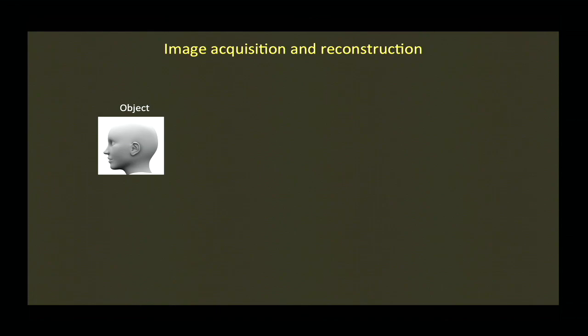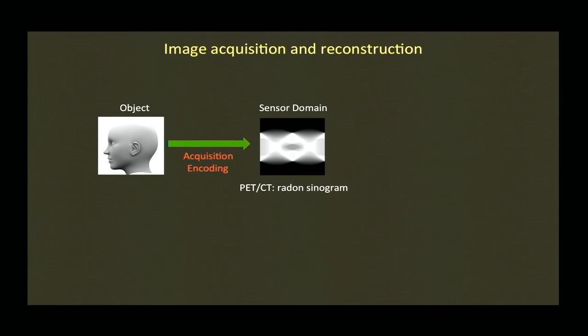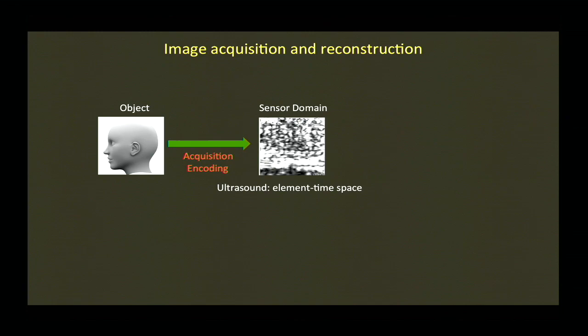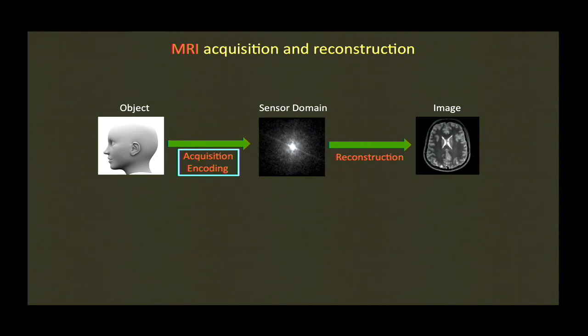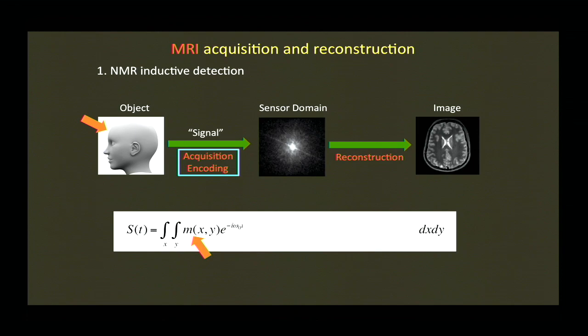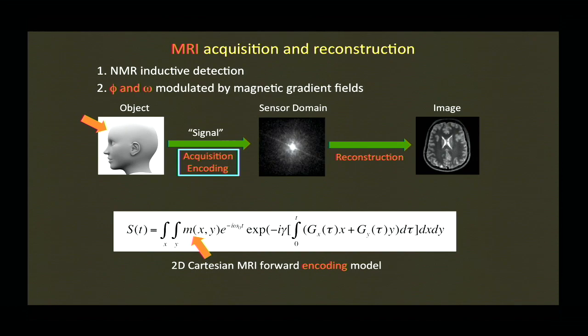To understand how we approach this, let's look at imaging independent of modality. You start with an object, forward-encode it into an intermediate representation — the sensor domain. The sensor domain could be a radon sinogram for PET or CT, element time-space for ultrasound, or Fourier k-space for MR. The reconstruction problem is simply inverting the forward encoding. For MRI specifically: you have some object, use inductive detection, and get a signal that you phase- and frequency-modulate by applying magnetic gradients. We immediately recognize this as the Fourier transform.